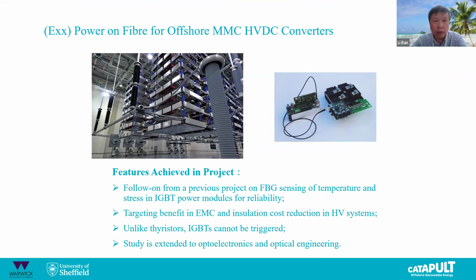This is about again reliability for MMC high voltage systems in general. As we know, IGBTs cannot be triggered like thyristors, and we have to maintain the gate drive signals, and it would be quite difficult to provide power supply in a high voltage condition because the insulation cost could be very high, and the electromagnetic noise could be difficult or expensive to handle. Therefore, we came up with an idea to provide the power supply to the gate drivers by power over fiber, using optical fiber. And that's about this project.